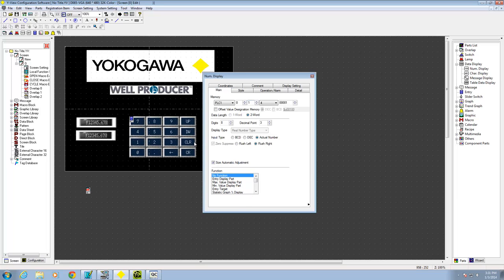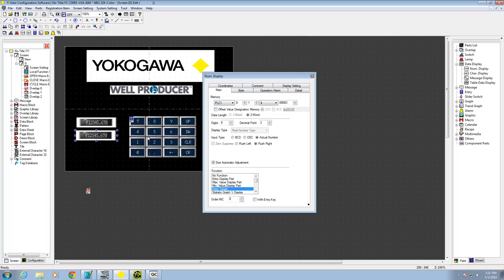Under function, go with no function since I'm just displaying a process variable as a read-only value. For the write variable entry display, it's again PLC 1, port 0, unit ID 1, but the address is 400003 — the holding registers I want to write to. Again, 2 words, actual number. This is set as an entry target, meaning the keypad can be used to enter a value here. If you had multiple entry targets on screen, you could flip between them using the up and down buttons.